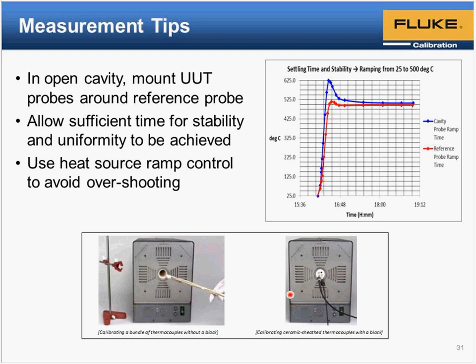But basically, the uniformity of the equilibration block setup is a little bit better, but there isn't as much flexibility as using the open cavity. So there are some costs there. Some people prefer the open cavity because they can put in a larger variety of probes, and they like to bundle probes, but they have to be careful with what the uniformity might be inside the furnace with these different configurations. The equilibration block is not simple, because you have to have probes that are long enough to go all the way into the end of the equilibration block, and there are 4 holes in the equilibration block.